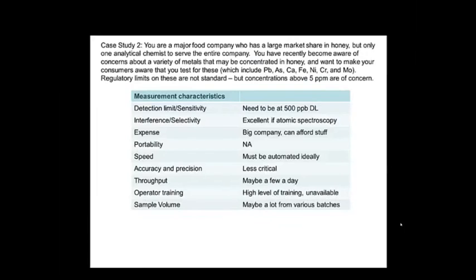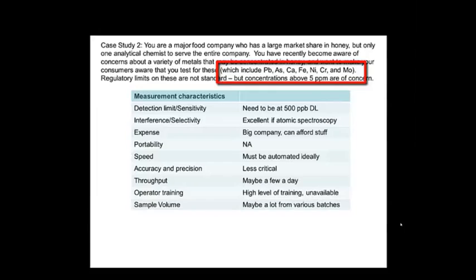Case study two: you're in a major food company with a good budget, and you have to measure a whole bunch of elements. You don't have regulatory limits, so you're after concentrations above 5 ppm, meaning a detection limit of maybe 500 parts per billion. You need to detect a lot of different elements, and it would be great if it could be automated. The really big driver here is that you've got to measure a whole bunch of elements at once, and there are really only two choices: ICP-AES (atomic emission) or mass spectroscopy. Since your detection limits are not really low, it would be overkill to go with ICP-MS — you'd have high infrastructure and maintenance costs. So I would probably go with ICP-AES.